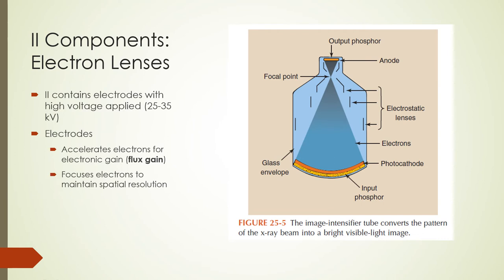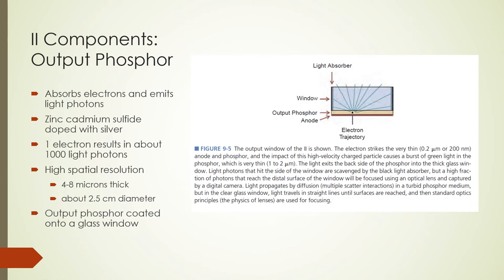Once electrons are released by the photocathode, they enter the vacuum chamber where they are accelerated by high potential differences of between 25 to 35 kilovolts applied across different electrodes. Electrodes shape and control the electron beam, forming what is called an electronic lens. Because of the increased electron speed due to acceleration, there is a so-called electronic gain or flux gain. The output phosphor diameter is about 1 inch compared to the input phosphor diameter of between 6 to 16 inches. The output phosphor absorbs the high energy electrons and emits visible light; it is made of zinc cadmium sulfide doped with silver, releasing about 1,000 light photons per absorbed electron. The output phosphor contains 1 to 2 micron size particles in a 4 to 8 micron thick layer and is coated onto a glass window.